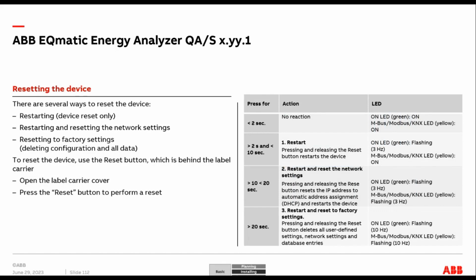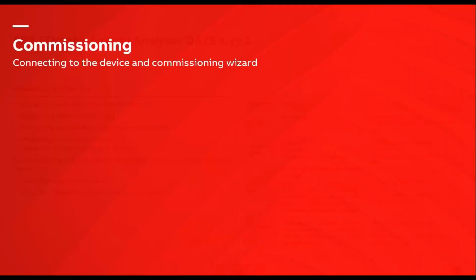Another useful piece of information: we can reset this device back to factory settings. There's a reset button hidden on the front behind the label holder. Press it for less than 2 seconds and nothing happens. Between 2 and 10 seconds, the device will restart. Between 10 and 20 seconds, we reset the network settings. Greater than 20 seconds performs a full factory reset.